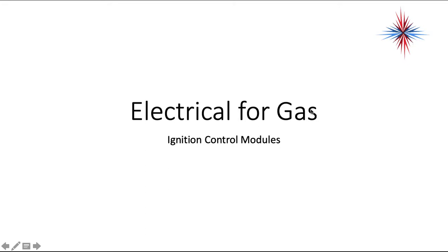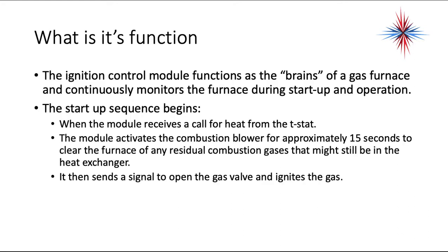In this video, we're going to talk about ignition modules. Now, once we're past the pilot version of the gas furnaces, which is the older gas furnaces, we start getting into electronic ignition, where there is either a pilot flame that's ignited by an electronic ignition source, or we directly ignite the main burners on a call for heat. But there's a control module that has to do this. This is called the ignition module.